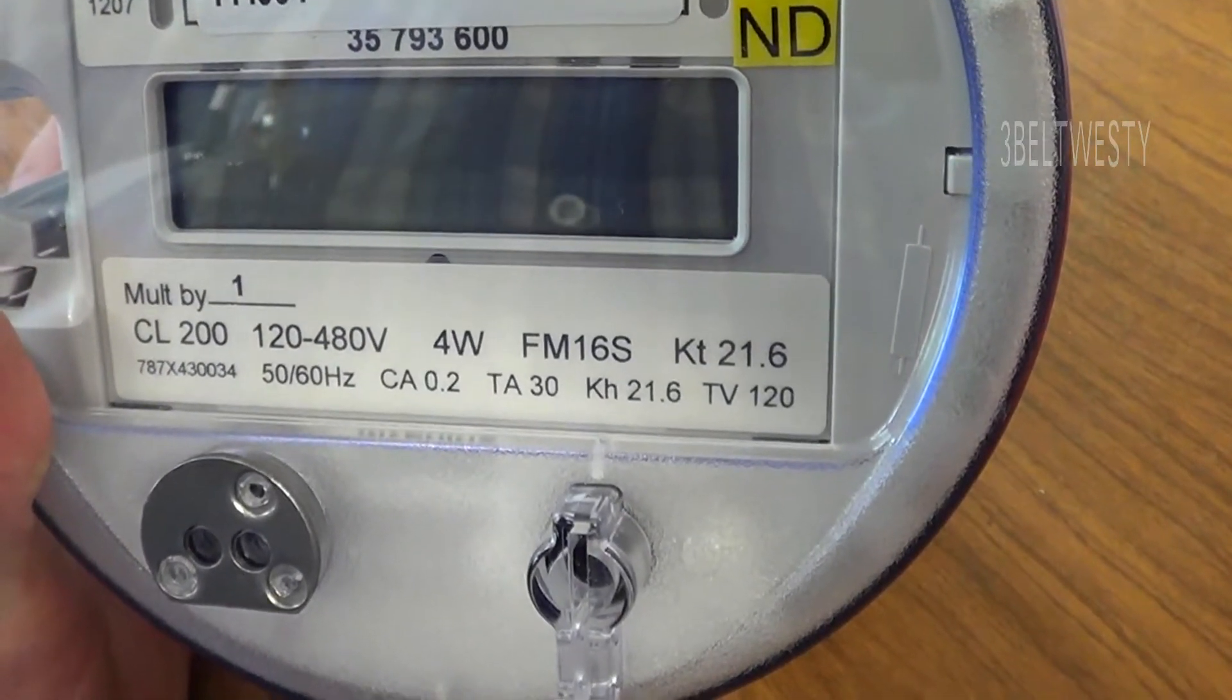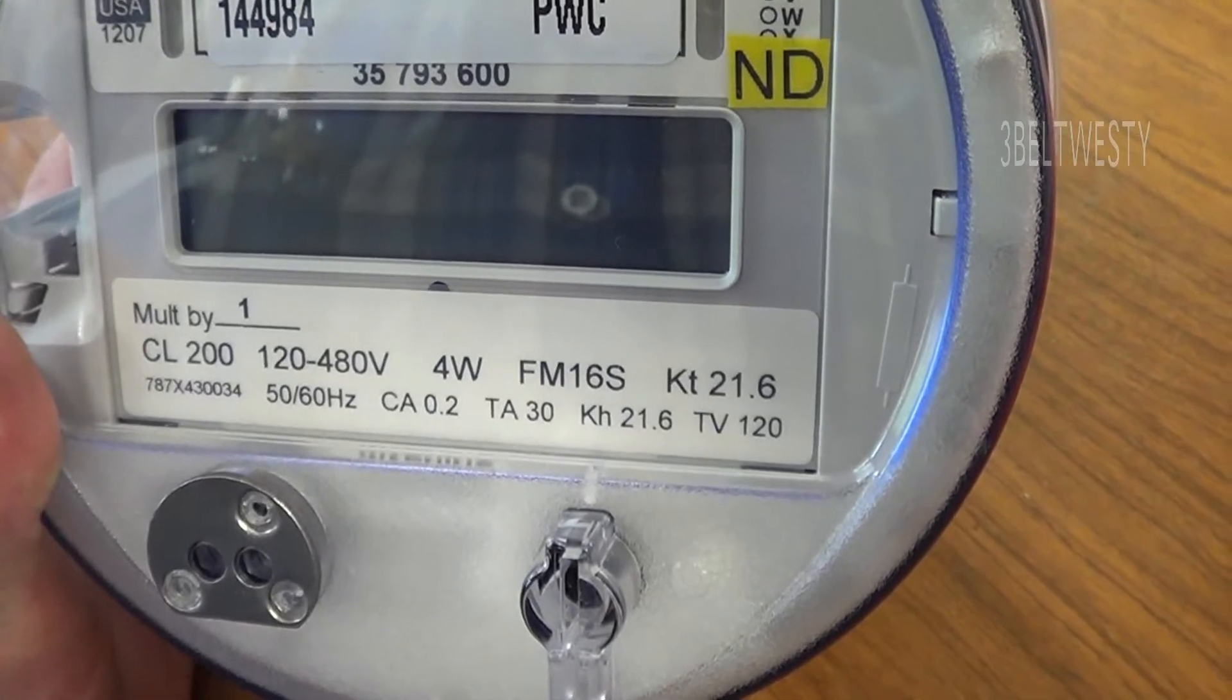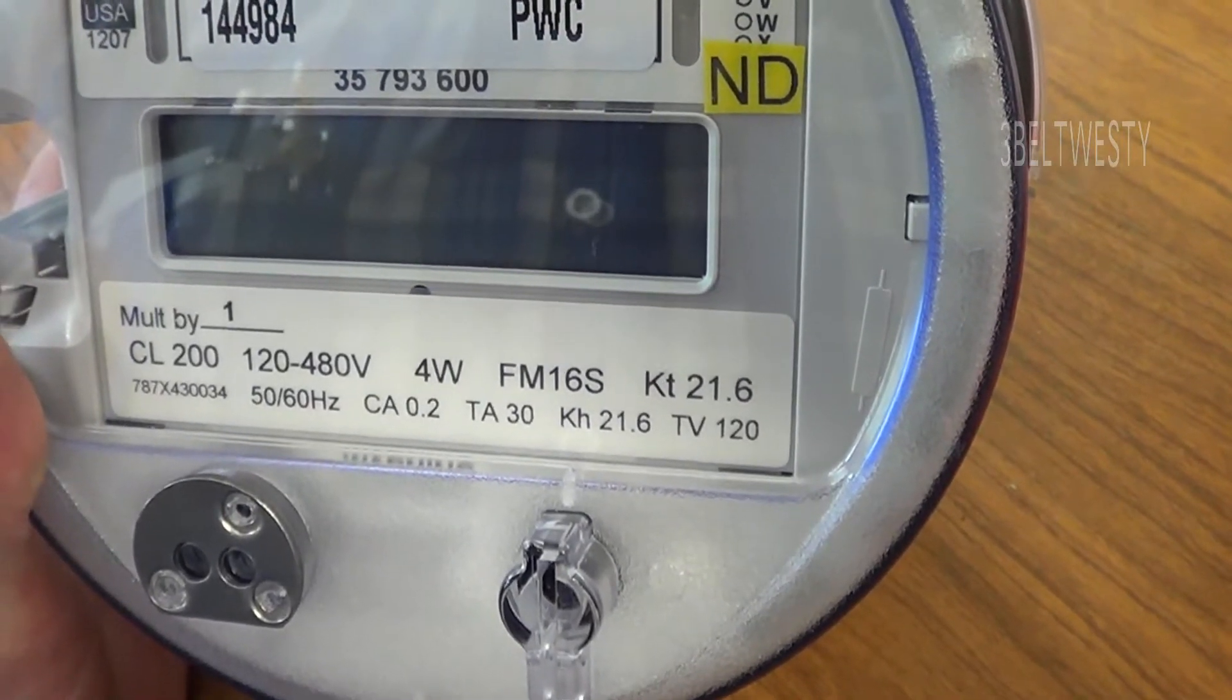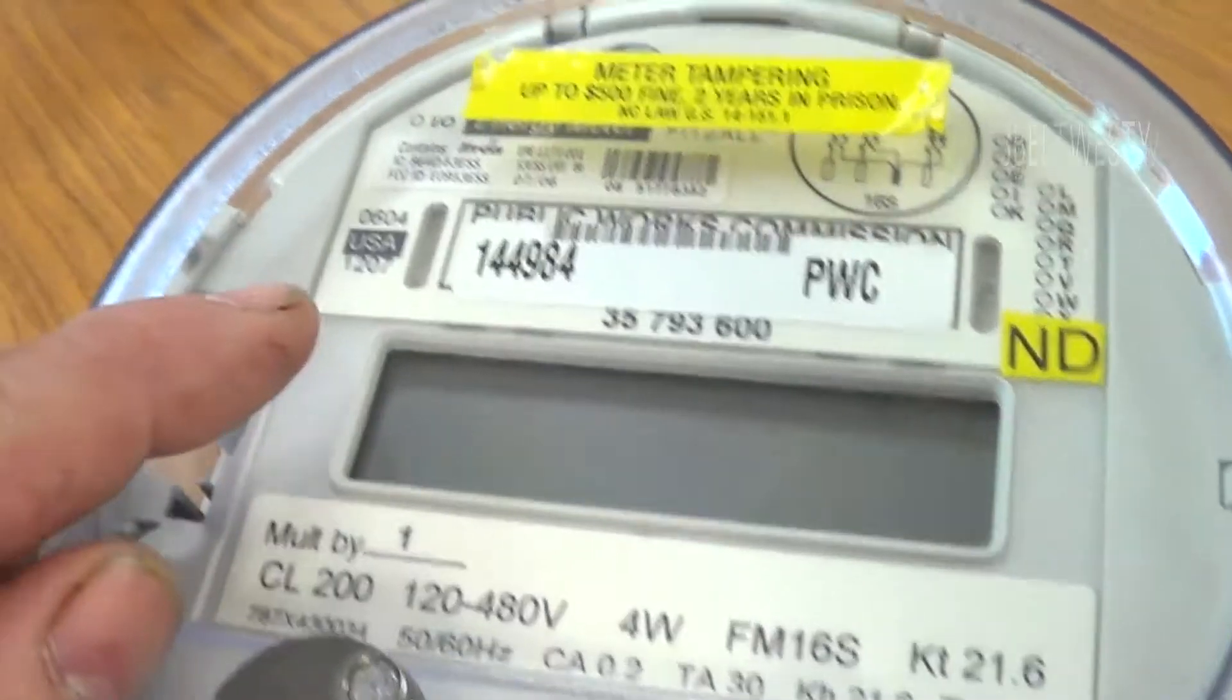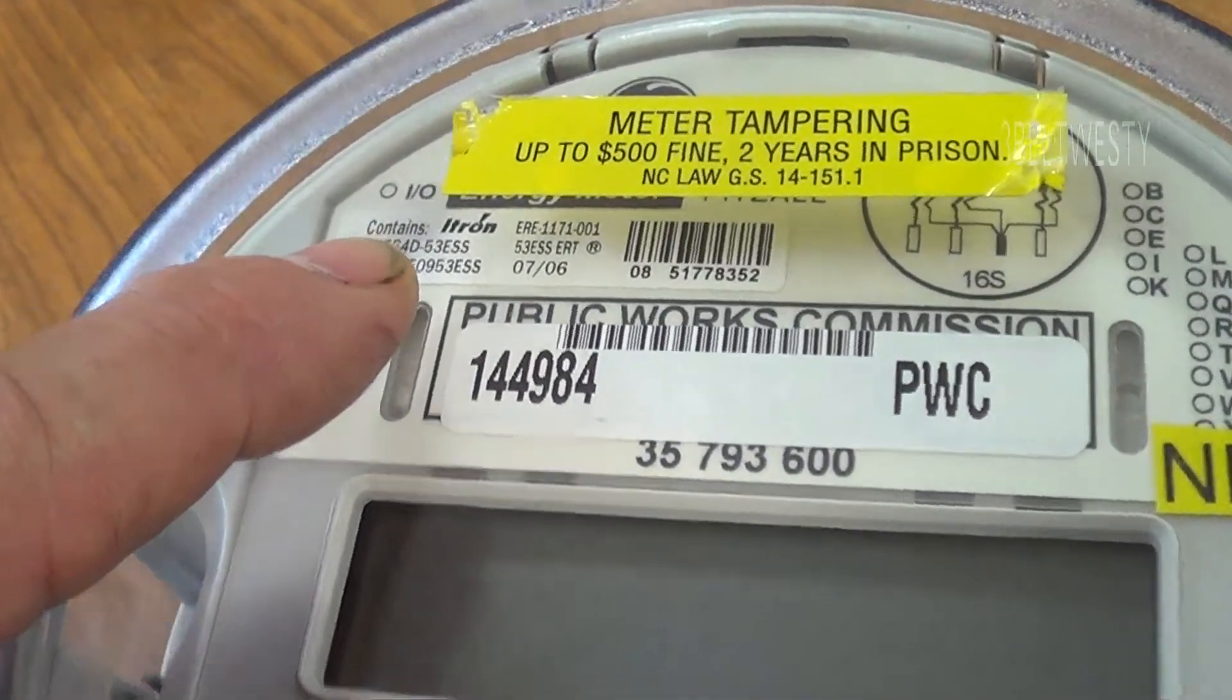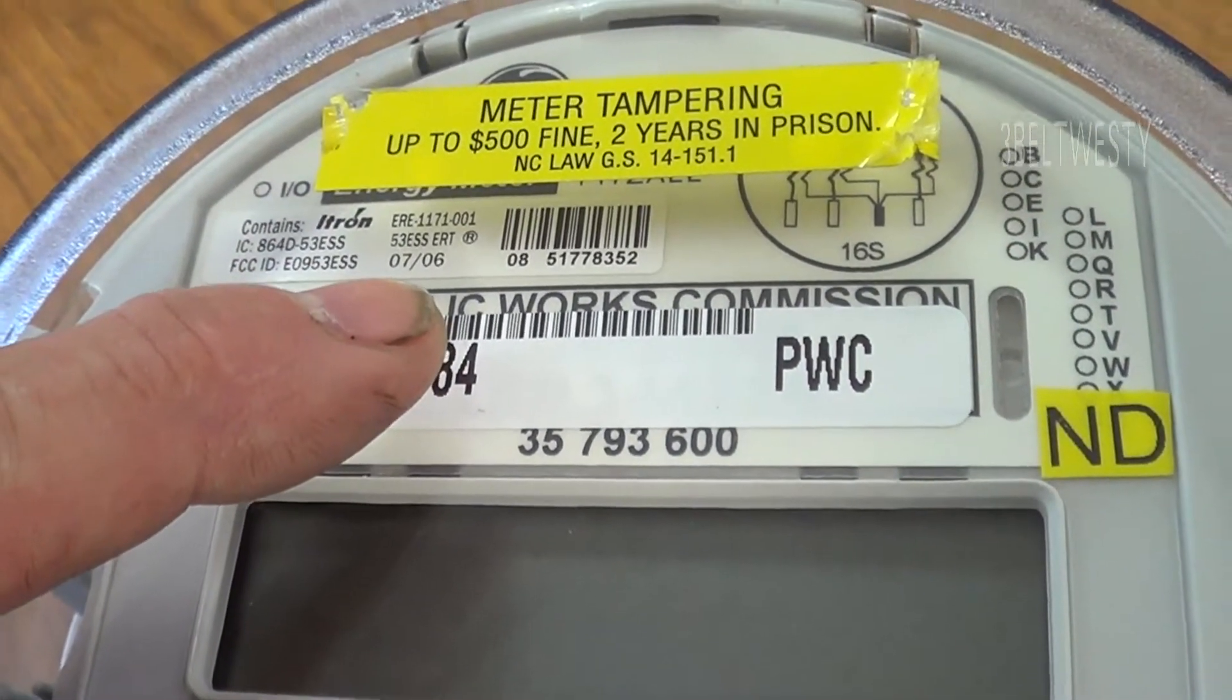This is a class 200 meter which means it has built-in meter shunts for the current four wire form 16s. There's KT 21.6, 50-60 Hertz, test amperes 30. This is the date that's manufactured 1207, there's a software rev and I believe this Itron, the FCC, that's the smart meter gizmo in there.